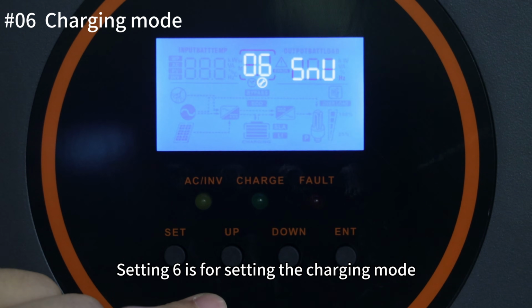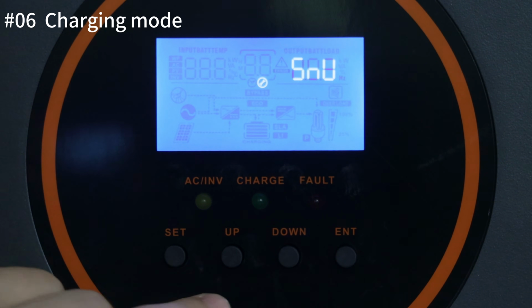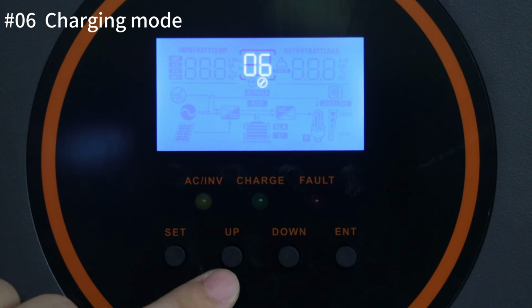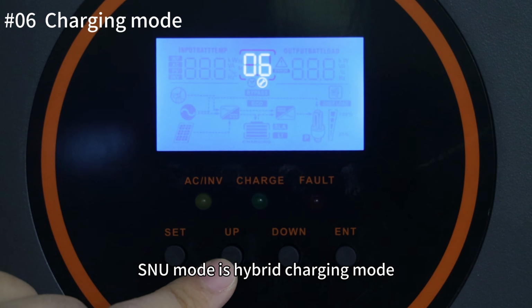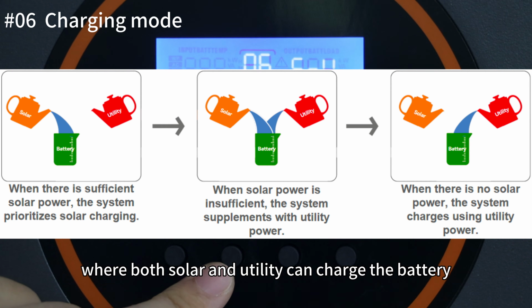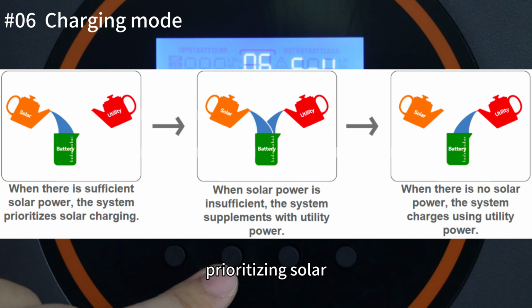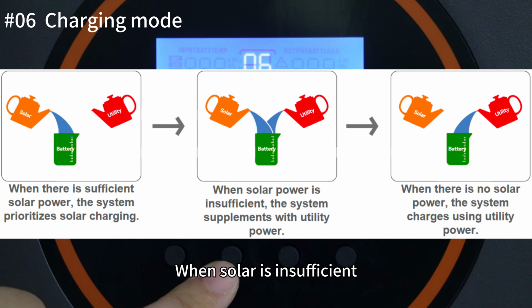Setting 6 is for setting the charging mode. SNU mode is hybrid charging mode, where both solar and utility can charge the battery, prioritizing solar. When solar is insufficient, utility supplements it.